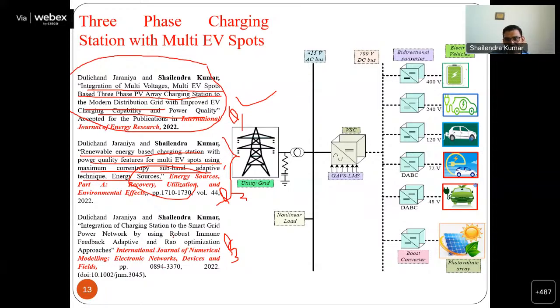What we observed is that when a large load is applied at the DC bus, the voltage drops. To maintain this voltage, PI control has a slower response since it's a proportional integral control. So in the third paper, we introduced a scheme like robust immune feedback adaptation combined with an optimization approach, so the voltage can be maintained and the controller parameters can be found such that they are automatically optimized.